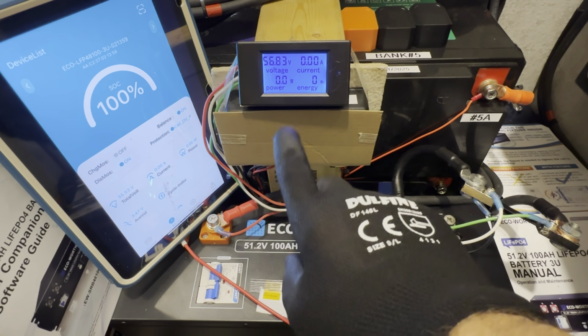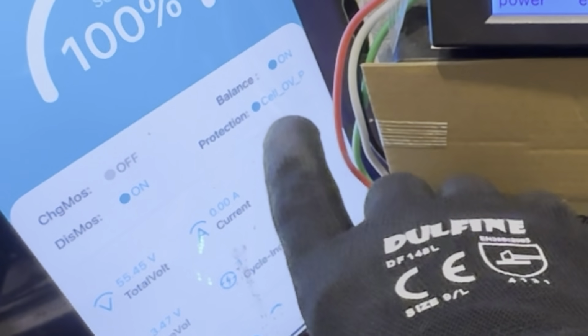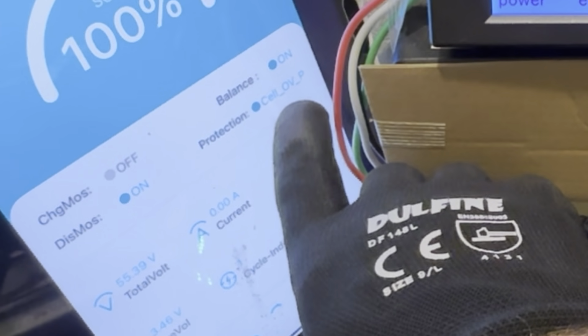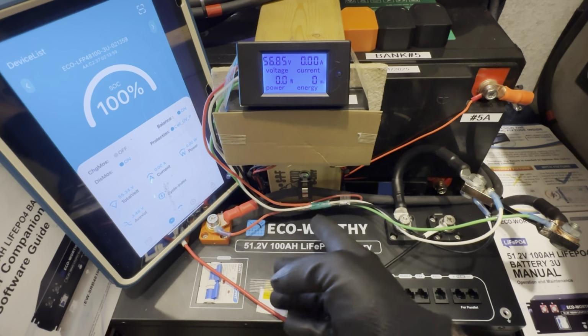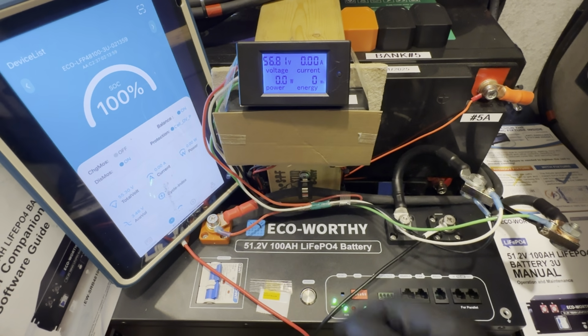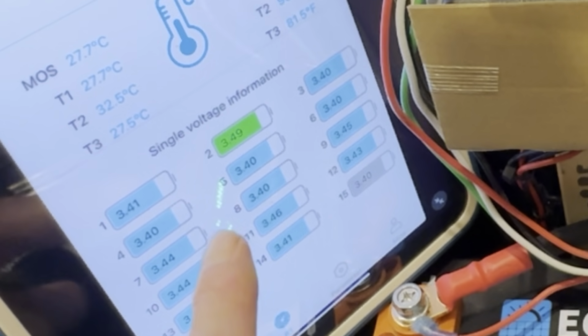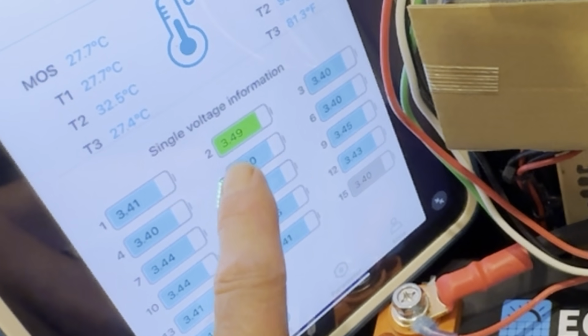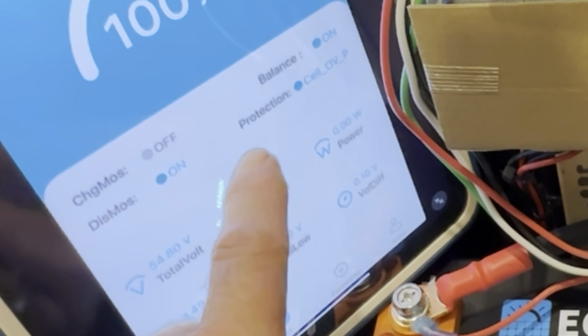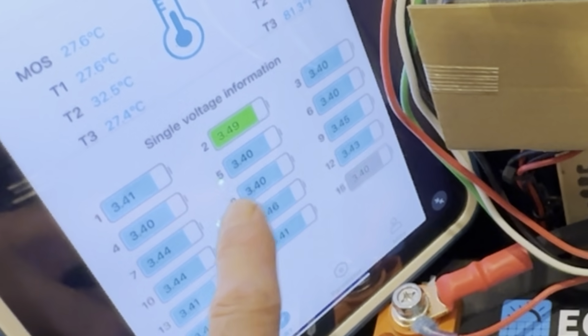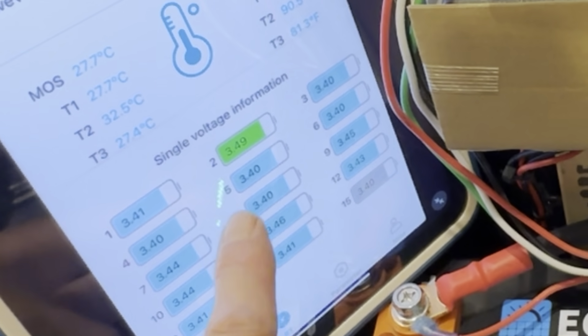Alright, the charger stopped right under 57 volts. The battery went off on a cell over voltage protection, so one of the cells went above its set point, so that's as far as I can fill the battery with the charger. Looks like cell number 2 is our potential runner cell because we're still on the cell over voltage protection. That one's still quite a bit higher than the rest of the cells.